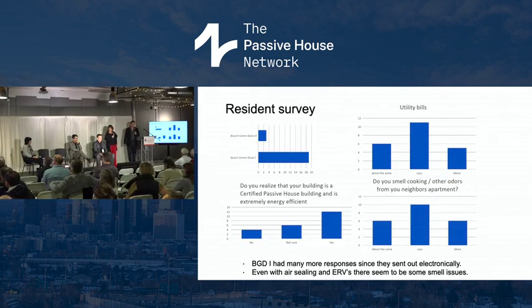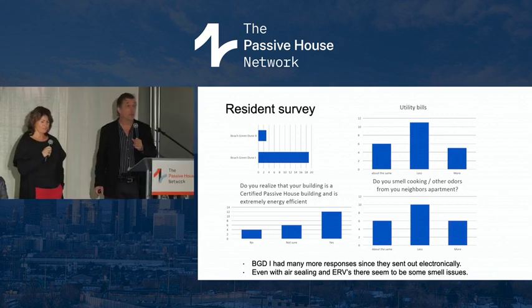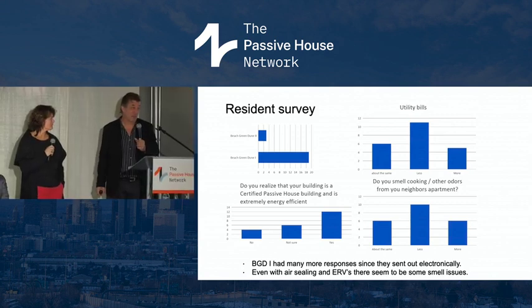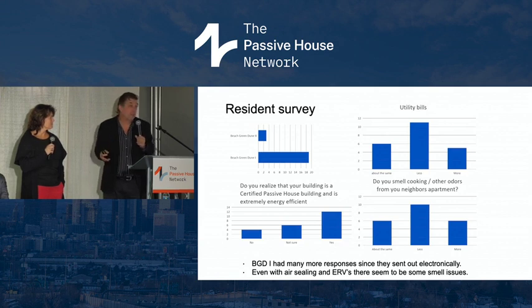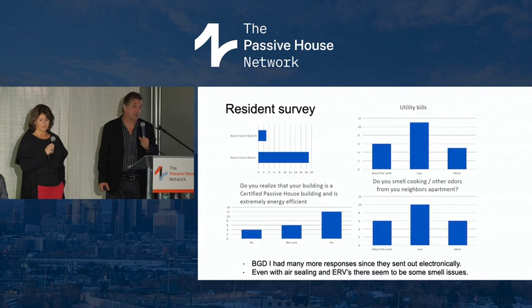In Beach Green Dune 1, we actually got some decent resident survey data, and we learned some things also tied with the super. People were complaining about smells, and we said, that's weird—we've got ERVs, they should be getting fresh air. People found that there was a circuit breaker in their panel, in their apartment, and since these units were unitized, if they turned it off it shut down the ERV. They said it doesn't make much difference, saves us $1 or $2 a month—but I understand. The side effect is they're not getting ventilation, and their smells, and their neighbors' smells, start building up.